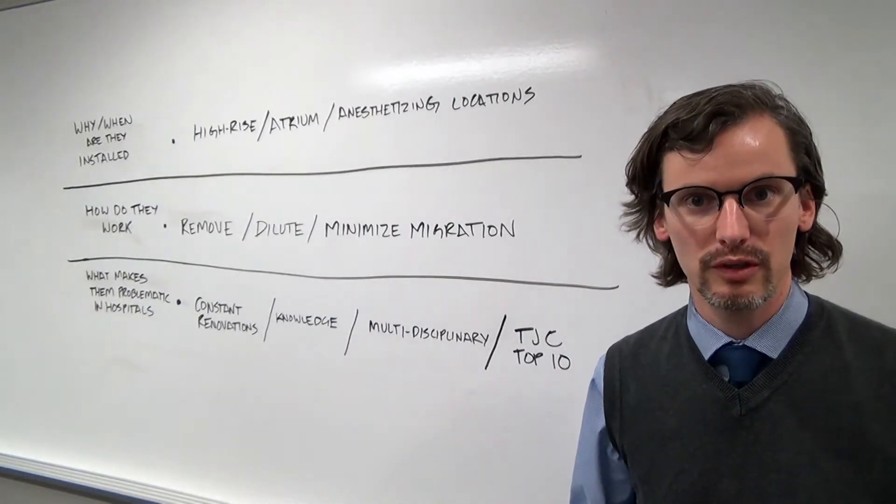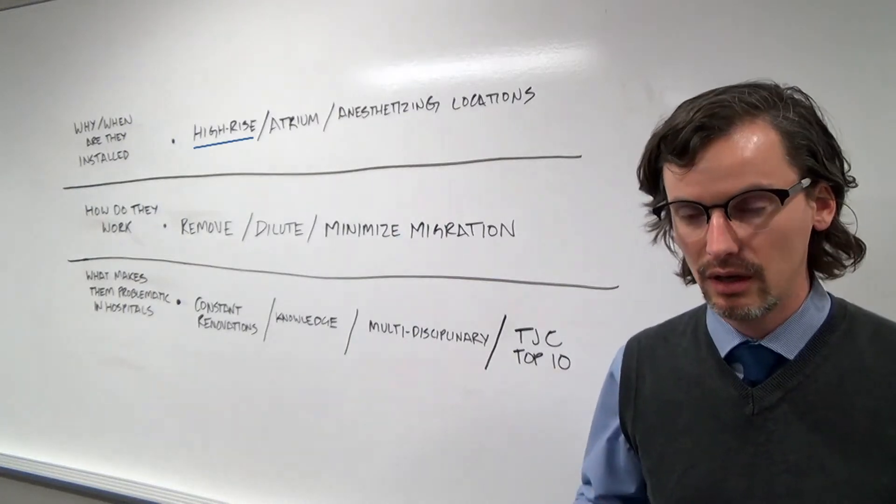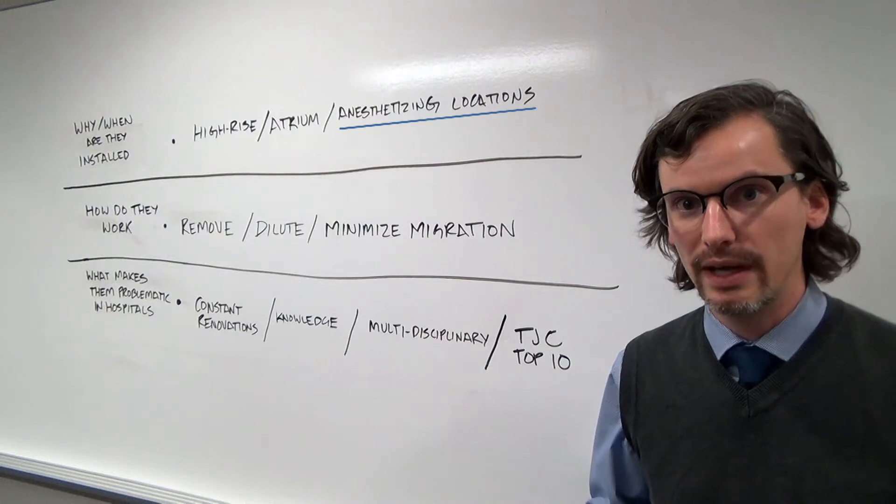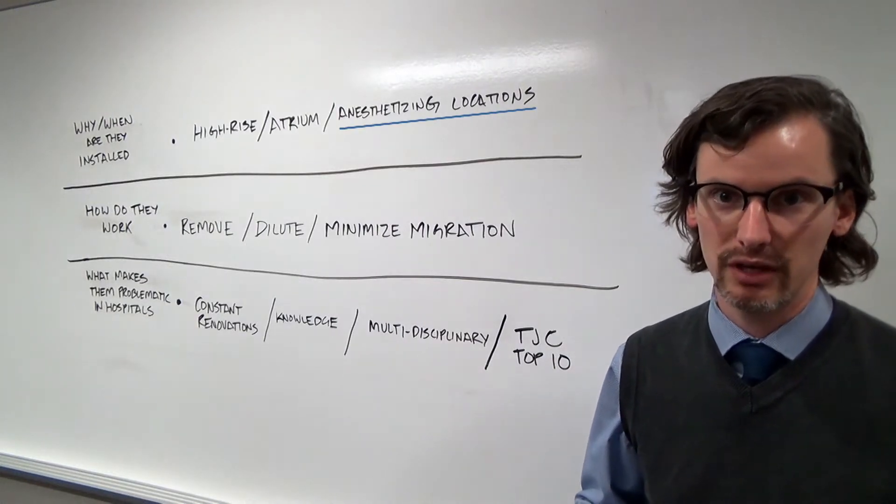Hospital smoke control systems are required in any high-rise occupancy, in atriums and clerestories, and any locations where inhalation anesthesia gas is administered.